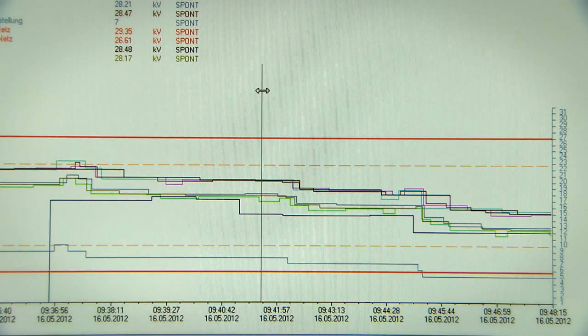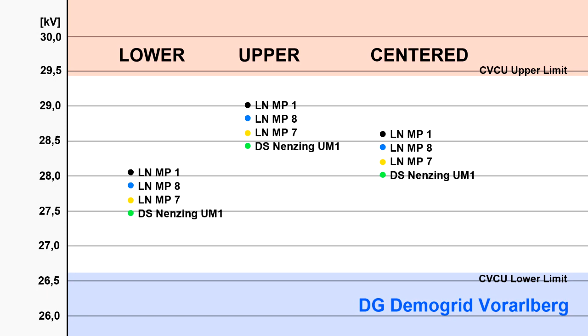For further optimization, the CVCU can operate in several modes according to specific requirements: lower limit, prevalence of energy input; upper limit, prevalence of energy output; or centered, for power quality maximization or minimal transformer tapping, to preserve the tap changer of the voltage transformer.